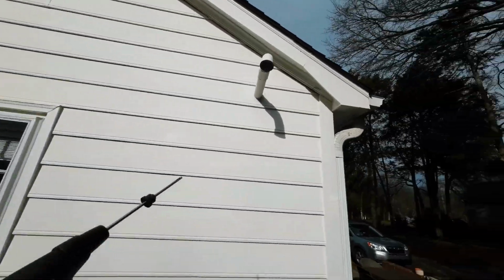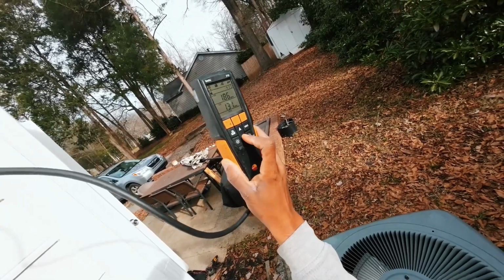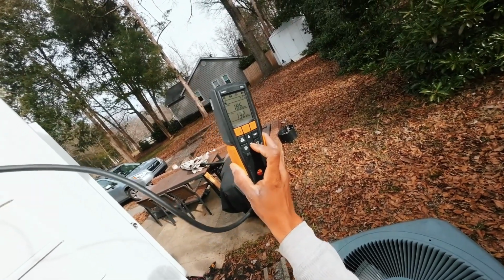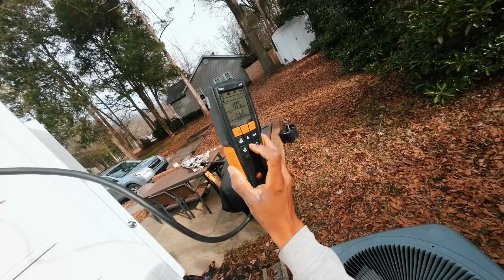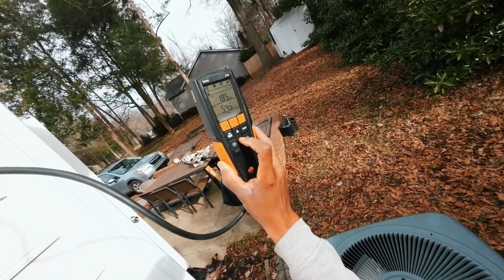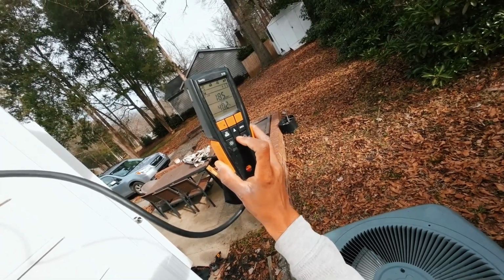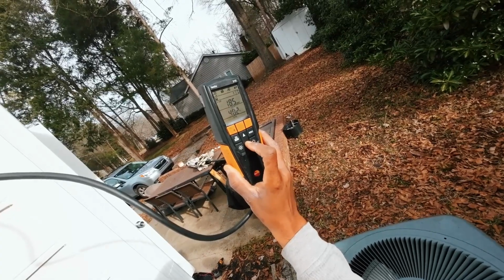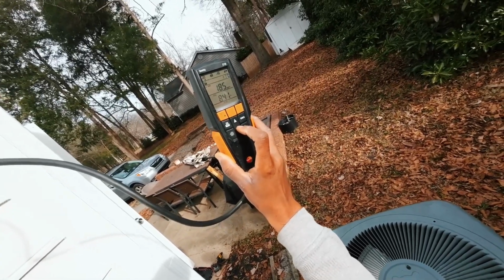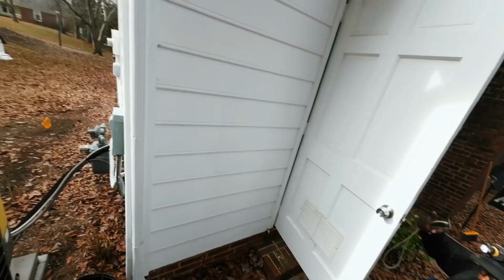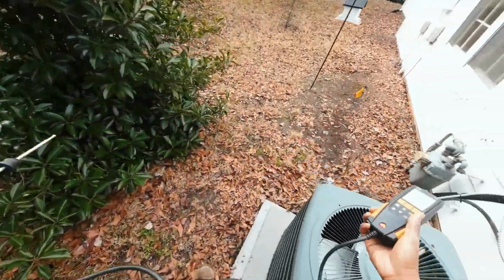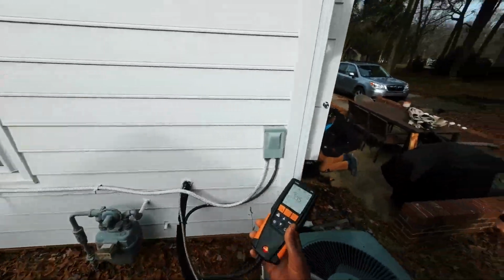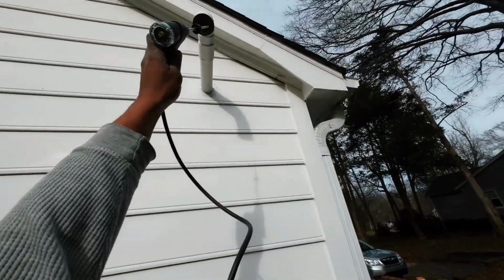So what we're going to do here, good thing is we've got access to it right at the outside, and our undiluted CO is almost 200 parts per million, so we're getting into the excessive ranges. Excess air 40%, that's respectable. A little low, but... Oh, you can check yours from out there? Oh yeah. Yeah, just don't turn that off while...